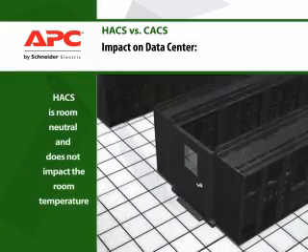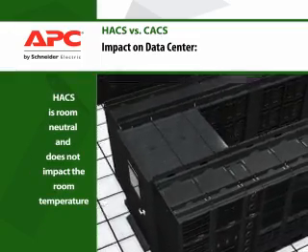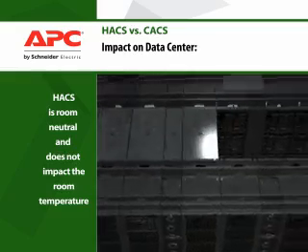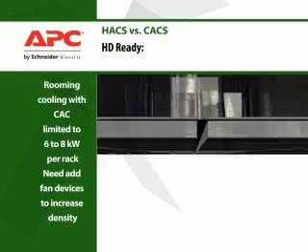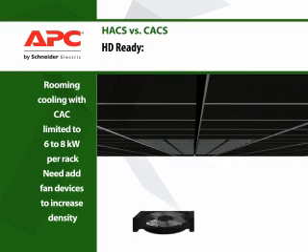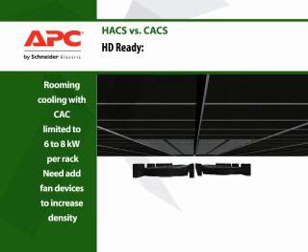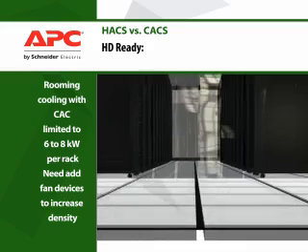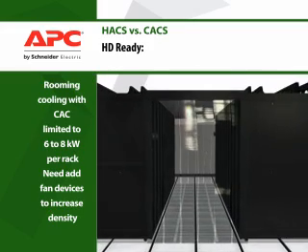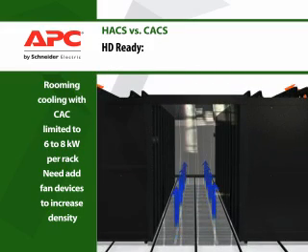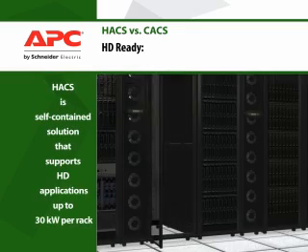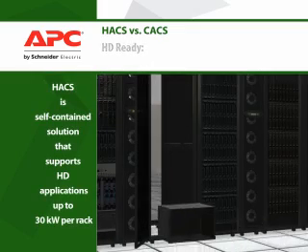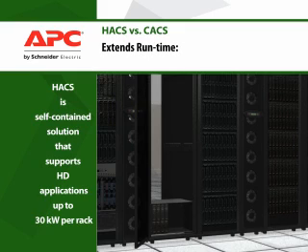The hot aisle containment system can easily be dropped in to any data center without impacting the data center environment. Typical raised floor systems only deliver enough cold air to support a maximum of 6 to 8 kilowatts per rack, and higher densities require specialized design or the addition of fan devices for proper air flow. APC's in-row cooling solution in the hot aisle containment system supports densities of 30 kilowatts per rack and beyond.